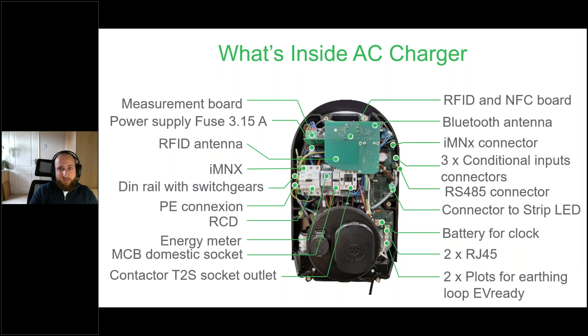This slide shows what's inside a typical AC charger — our EV ProLink AC unit. Our ProAC chargers are targeted for commercial or public use, so they're a little bit bigger than your typical domestic charger. Domestic chargers can be smaller because they're just a socket on the wall. These units build in different parts like the MID meter and built-in RCD protection, as opposed to having these parts further upstream. The built-in RCD is for extra protection, minimizing fault currents. We've also got a dedicated RFID and NFC board, which allows users to activate charges with RFID cards — if they've already got security passes we can loop that authentication in, or charge point operators can provide different RFID cards for their users.